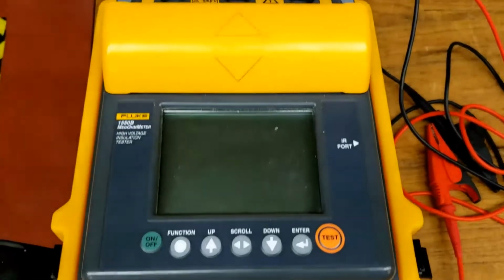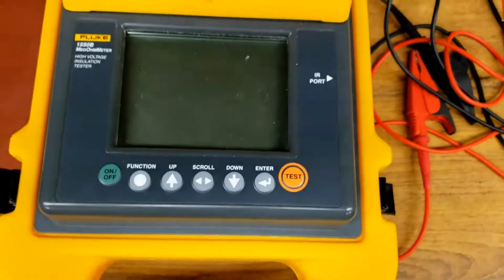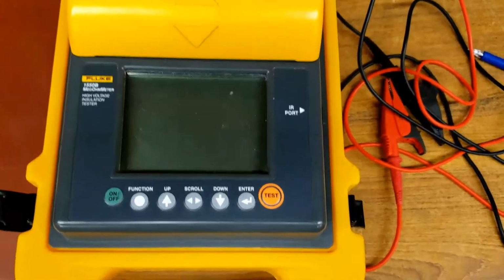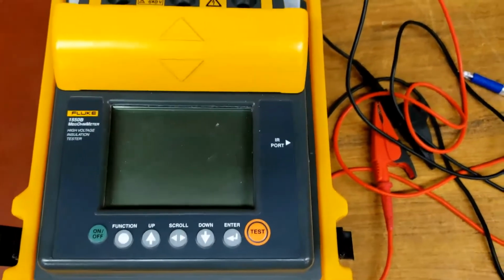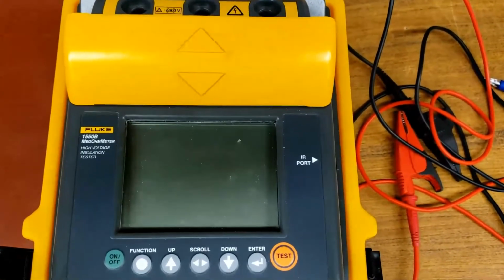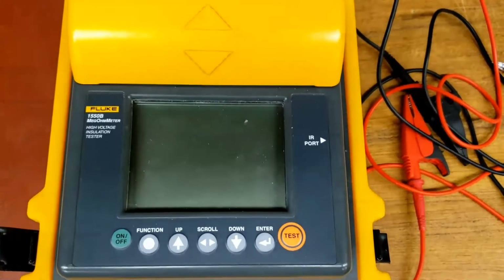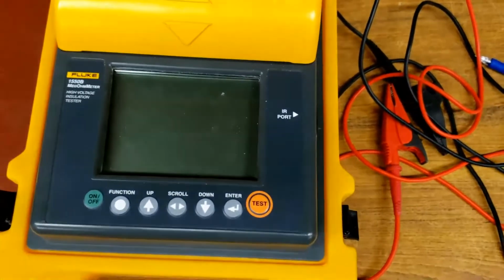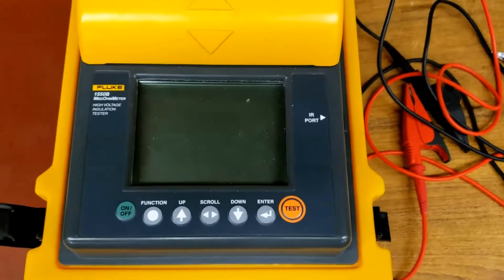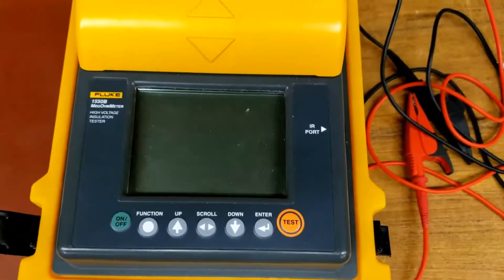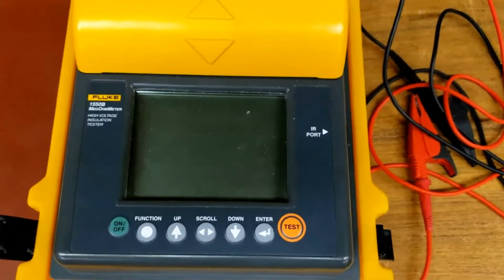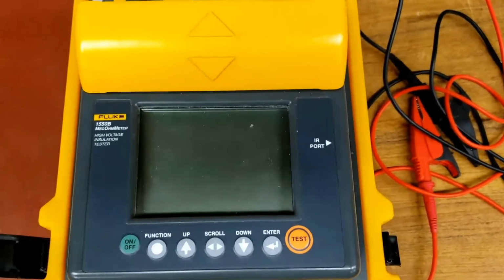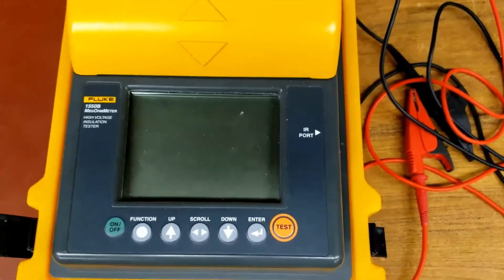This is our Fluke megger. The megger is an ohmmeter that can test at a very high voltage, several thousand volts. So what it will also do is stress the insulation, and if there's bad insulation, the voltage is high enough to arc through and create some current flow, which is then measured. It does the math and tells you what the effective resistance is, but basically it's measuring the current flow.